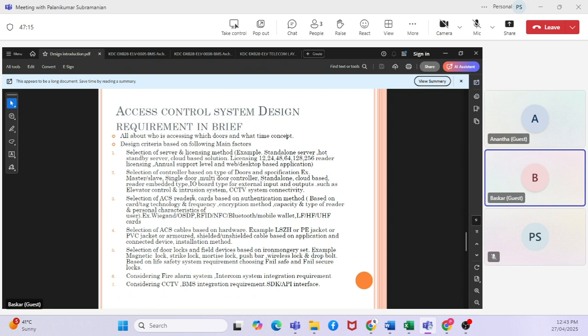You have master-slave controllers. If you're in a single premises, you can go with master-slave. But if the client and consultant are looking for an IP based solution, then all controllers should be IP based - there should not be a master-slave concept. As the name states, the master gives commands to the slave, so the slave doesn't have any brain. In case the slave fails, all doors connected to that slave fail, and we are out of control.